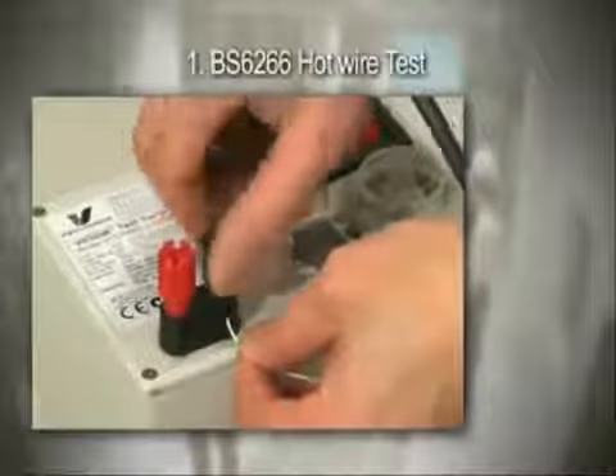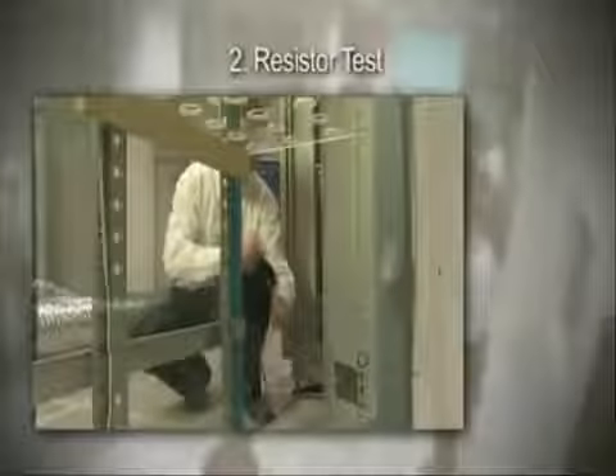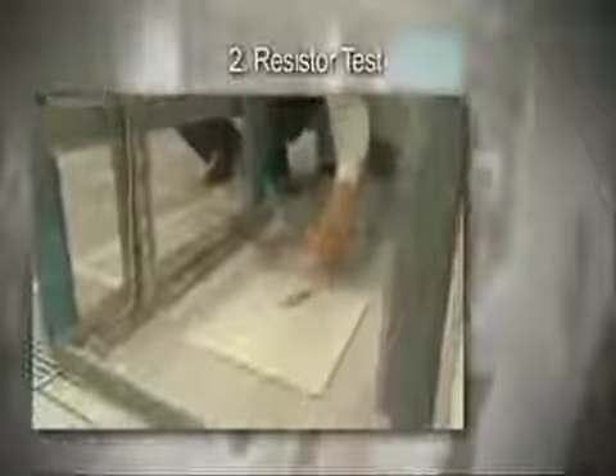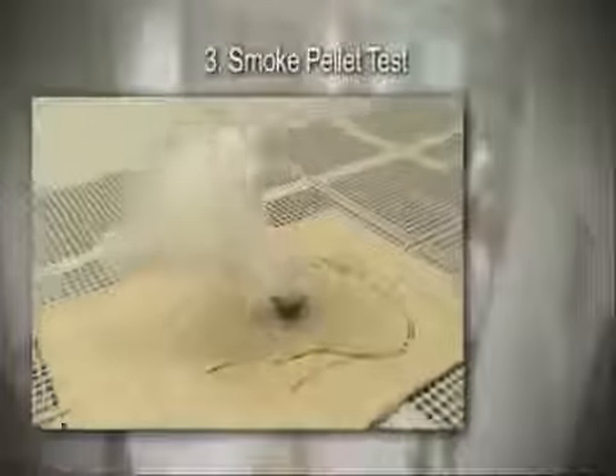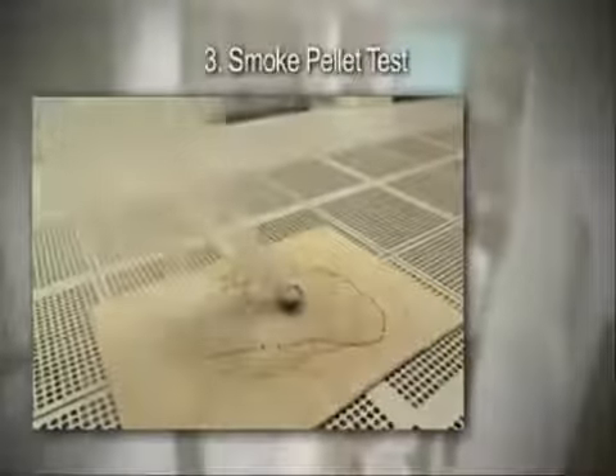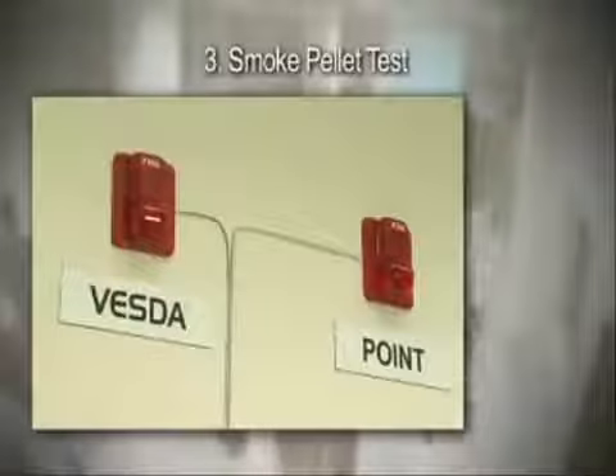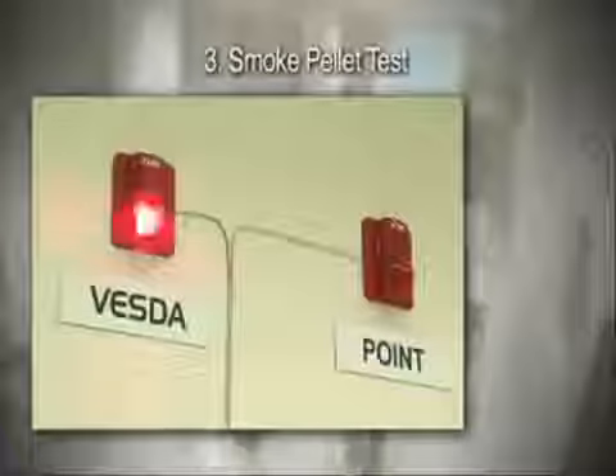The first test method produces an initially slow-growth smouldering fire, similar to overheated PVC-coated electrical wires. The second test method produces a short period of smouldering smoke, similar to an overheating resistor on a circuit board. The third test method produces a large quantity of smoke and is used to imitate a fast-growth fire. Both detectors were programmed to trigger the strobe sounder at the fire alarm level.